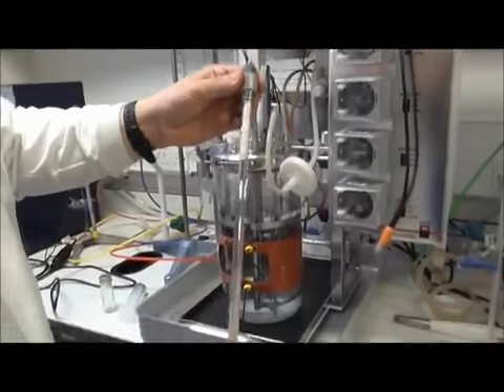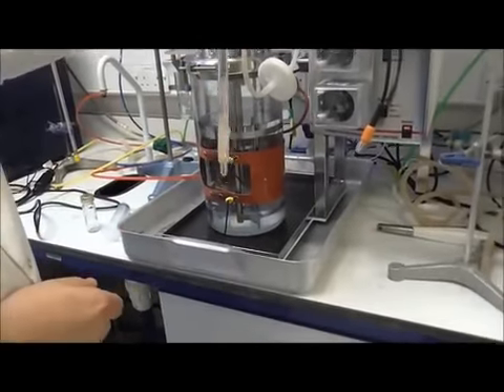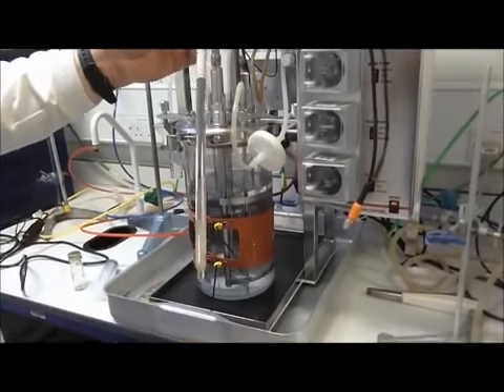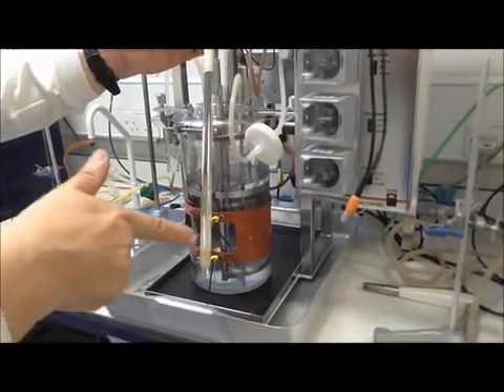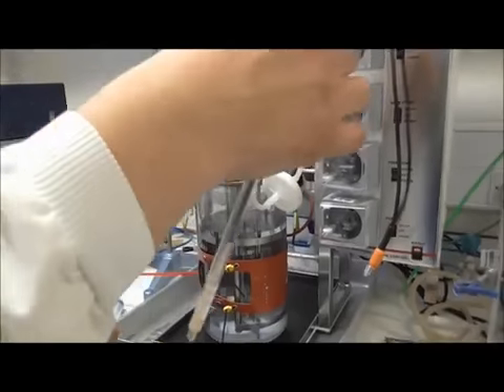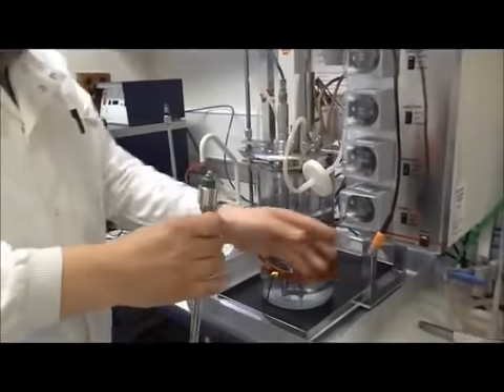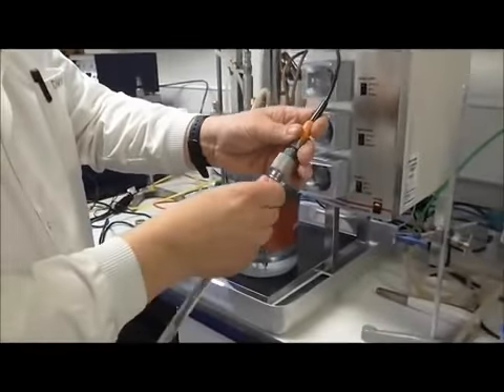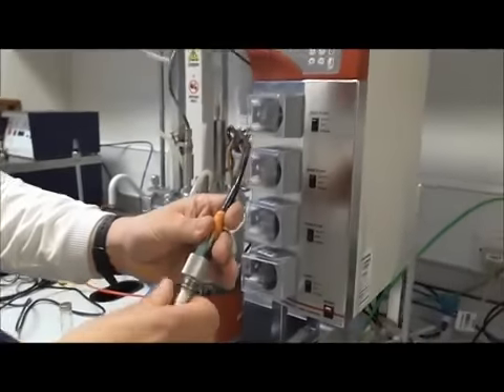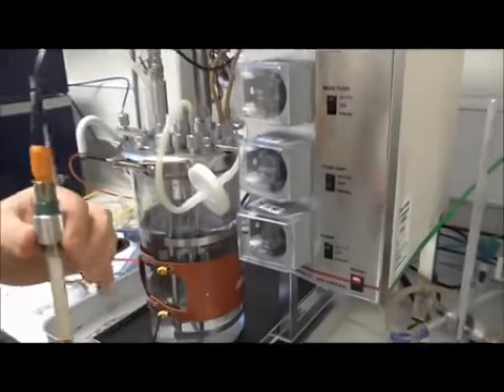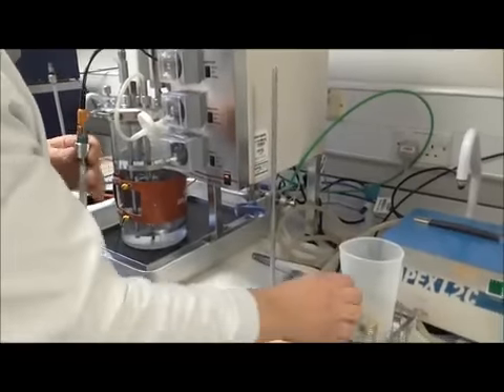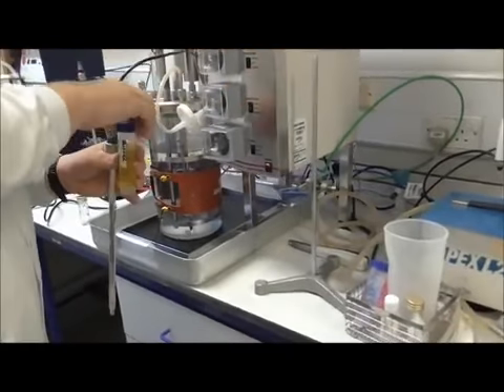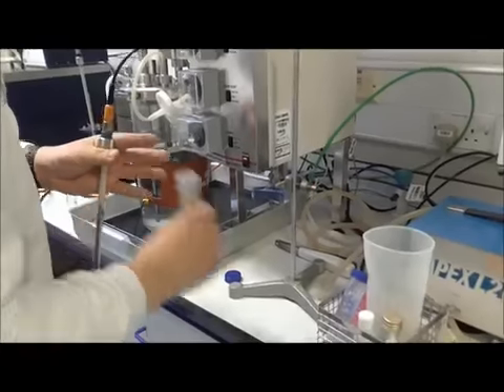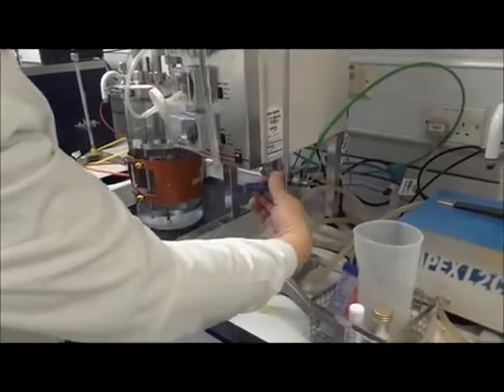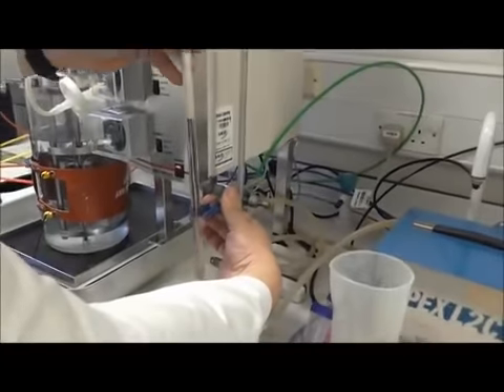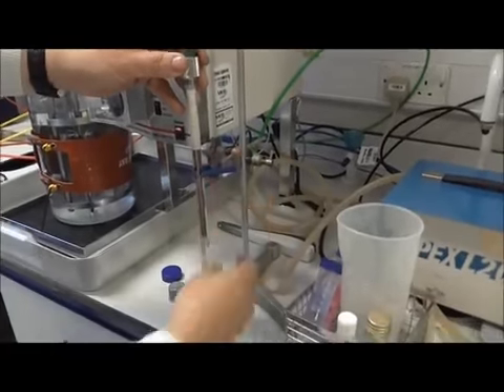It's a sealed probe. There is an electrolyte gel in here which does discolour, it does crystallise, hence you can see a bit of crystallisation down here. Do not be alarmed, it does do that, and it does work. So we reconnect to the lead and we get our buffer number 7 ready. And we secure the probe in the clamp and pop into buffer number 7.